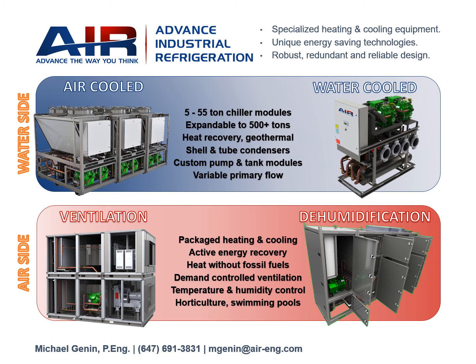If you look at the exhaust or cooling coil, the cooling coil is extracting just like any cooling coil. It is doing both a sensible and latent portion of the load as that vapor in the air condenses in the coil and moves down to the drain pan. So active heat recovery is extracting both sensible and latent energy, and it is better than a desiccant wheel at extracting latent energy, but it is technically converting both sensible and latent energy to sensible only energy through the compressor. The condenser coil can only add sensible energy to the supply air stream, and that's an important thing to distinguish: you're only adding sensible energy to that supply air stream.